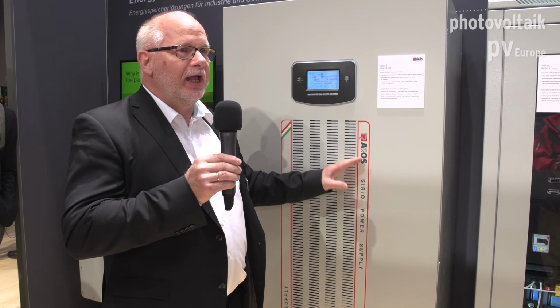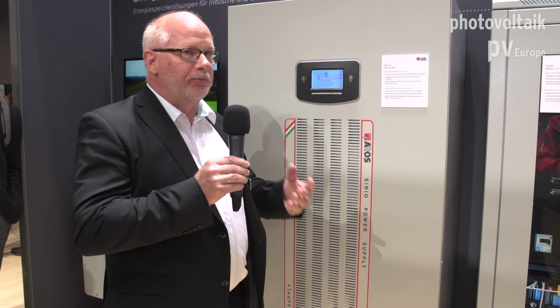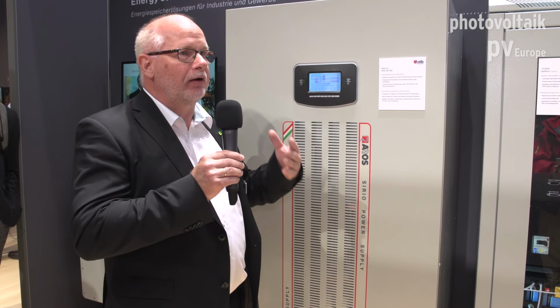That is very high, because we have the possibility to take, as an example, 100 kilowatts out of 25 kilowatt hours. This is important because we are talking about a UPS system. If we are on battery supply without mains, the UPS or energy storage must be able to supply the complete energy out of the battery to the inverter, to the load. And also if we have a short interruption, or a very big peak, that must also be handled from the battery. So it's important to have a C rate of 4.